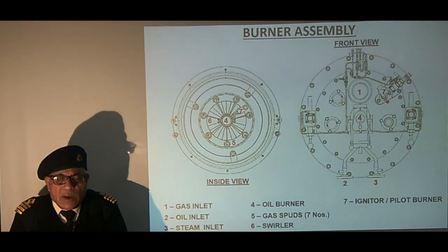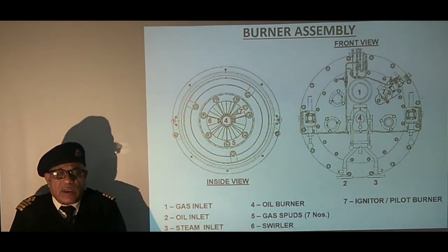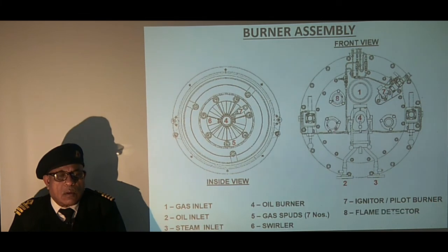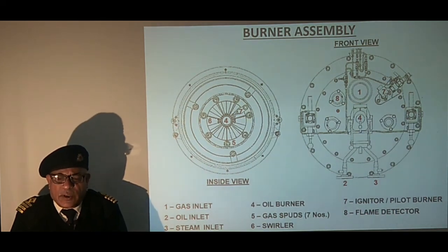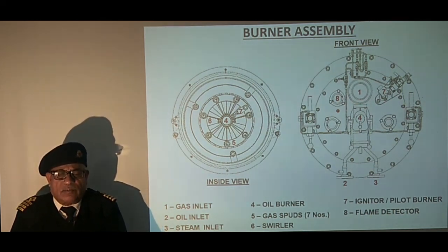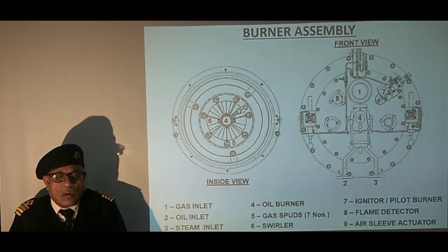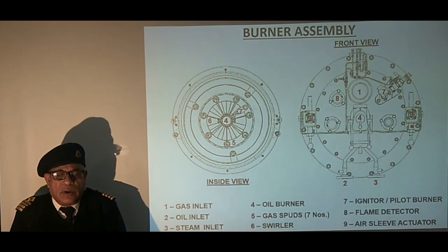For lighting of the burner, a pilot burner of pressure jet type is used for which diesel oil is supplied by the ignition pump at 6 bar. A spark is provided by the igniter through high voltage discharge. A flame detector monitors the flame and shuts down the oil and gas burner if the flame is extinguished. Pneumatically operated cylinders are used to shut off the combustion air after stopping the burner.